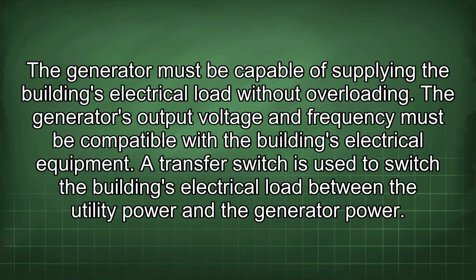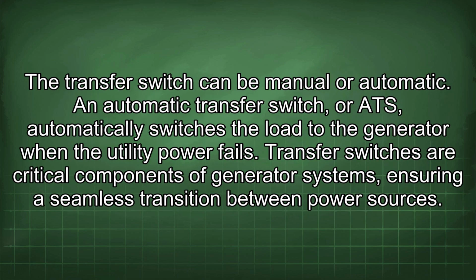A transfer switch is used to switch the building's electrical load between the utility power and the generator power. The transfer switch can be manual or automatic. An automatic transfer switch, or ATS, automatically switches the load to the generator when the utility power fails. Transfer switches are critical components of generator systems, ensuring a seamless transition between power sources.